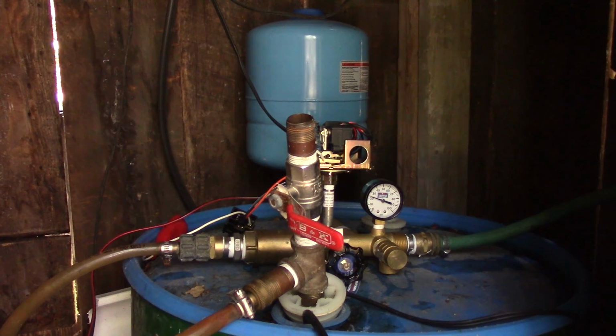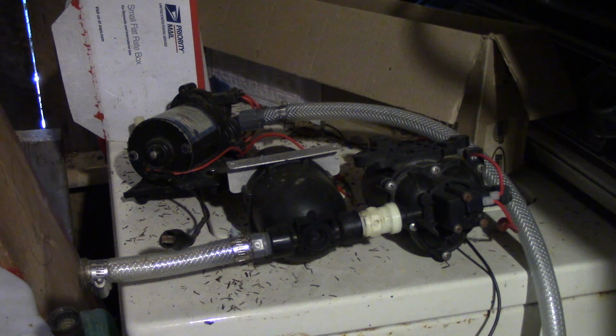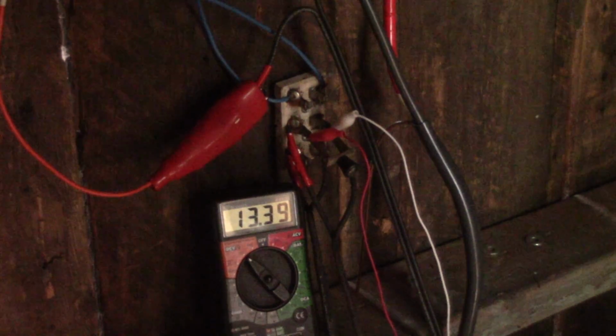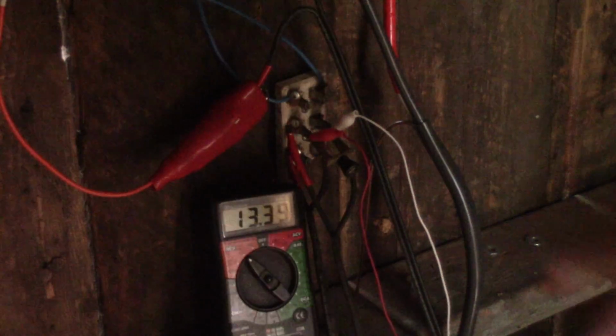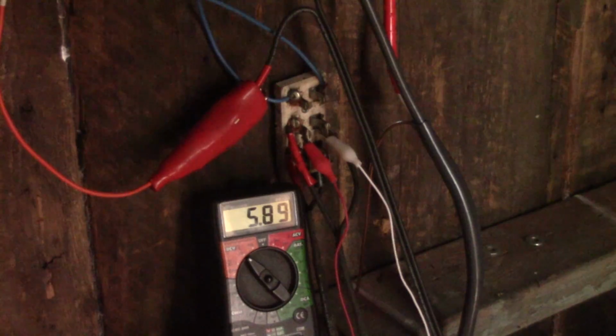You might remember that last year I modified the way I pumped my water at the cottage. I did this because I was not satisfied with the way my other pumps were pumping. Well, it's not working any better, and I figured out why. When the pump starts to work, I lose almost all the voltage. I didn't think of this when I did the wiring, but it's normal.